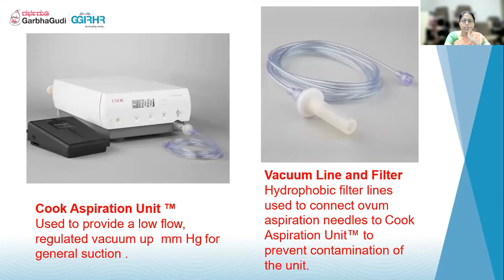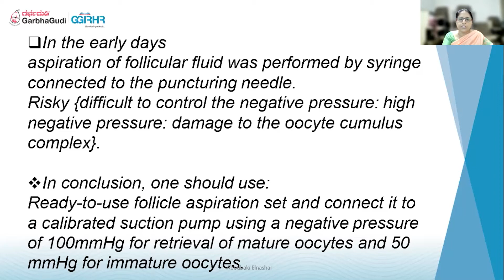So the Cook aspiration unit has everything neatly packed in this one. It helps a lot in oocyte retrievals. In the initial days, what they were doing is connecting it to a 20 ml syringe and operating with the thumb handle. But it was very difficult to control the negative pressure and it used to damage the OCCs. Always better to use the follicular aspiration set. Keep the pressure less than 100, and less than 50 for immature oocytes.